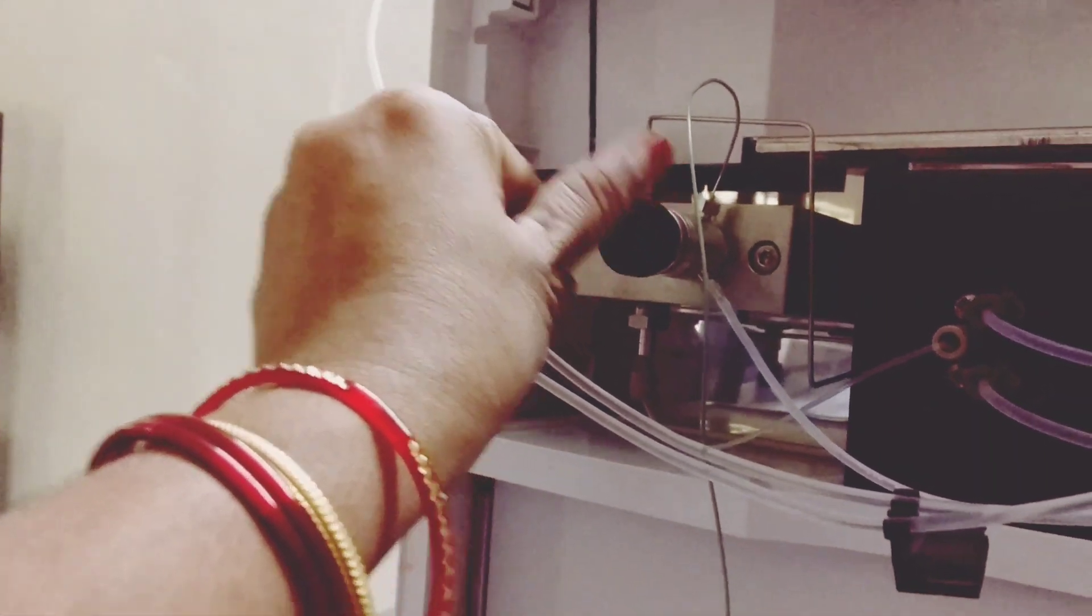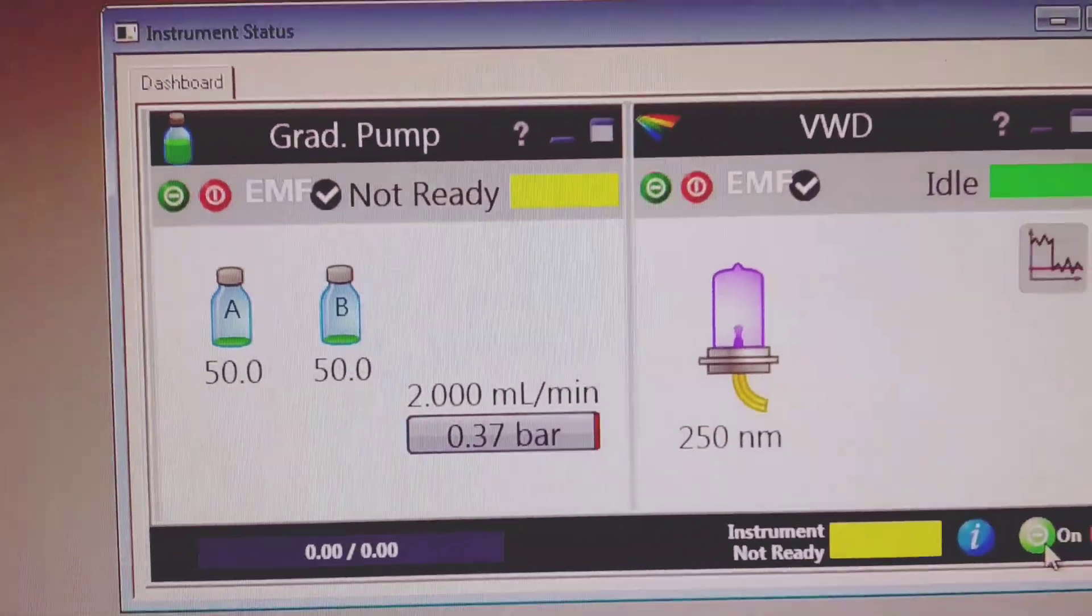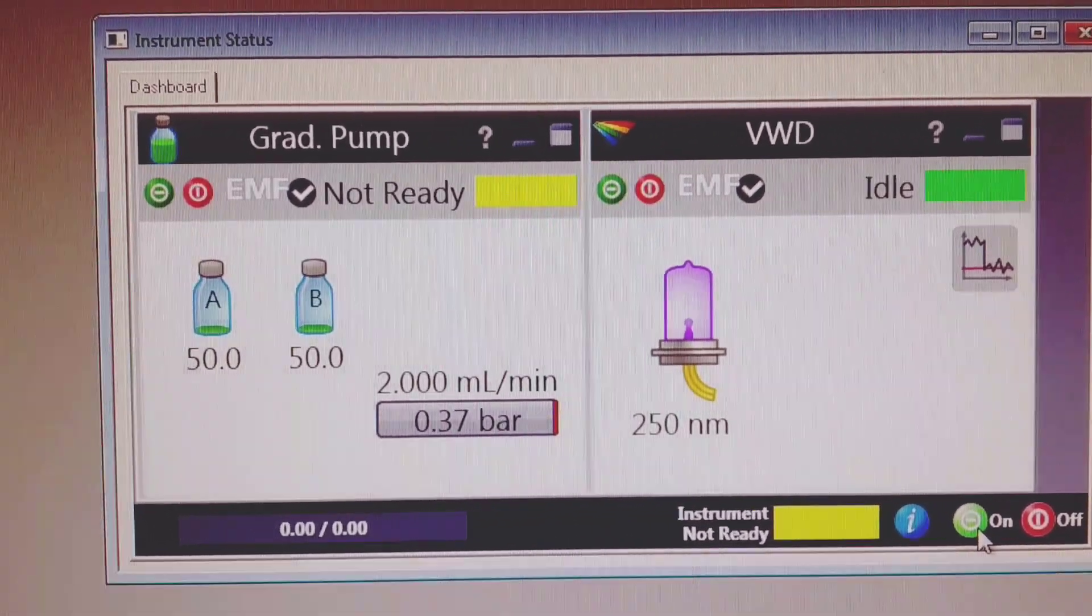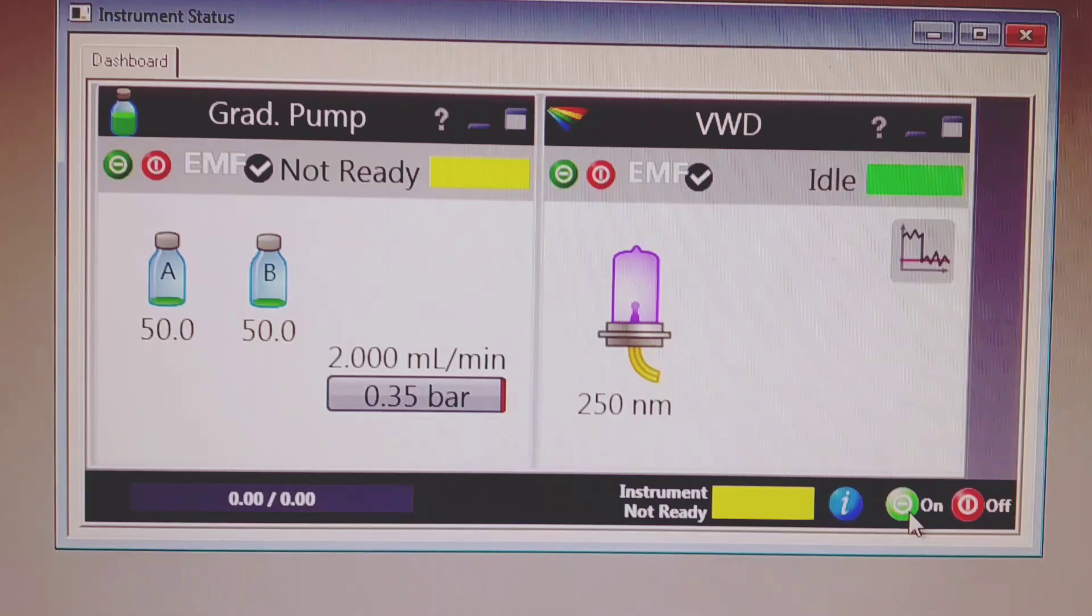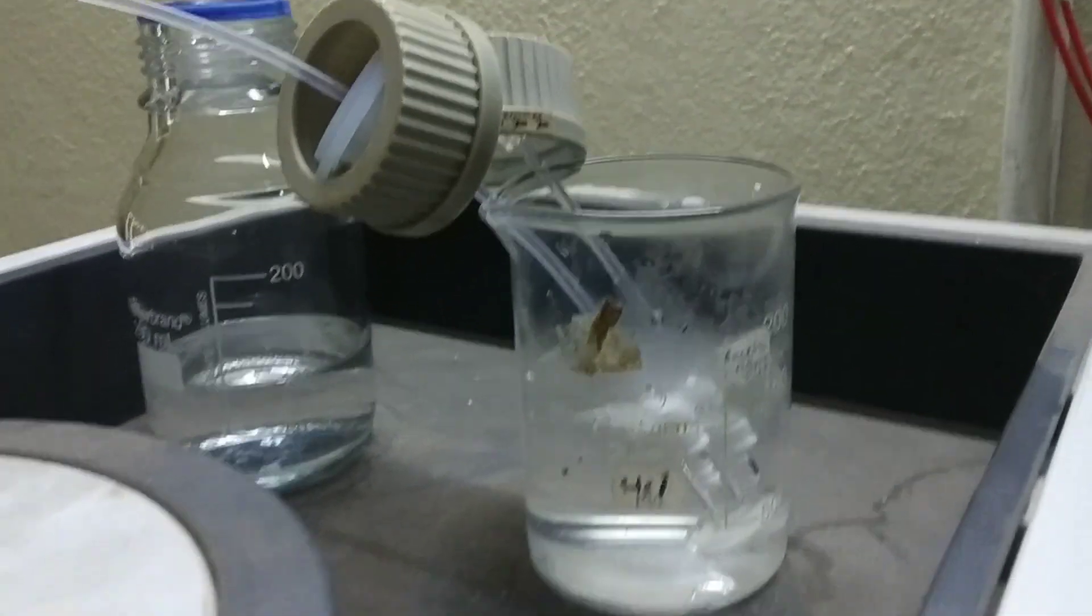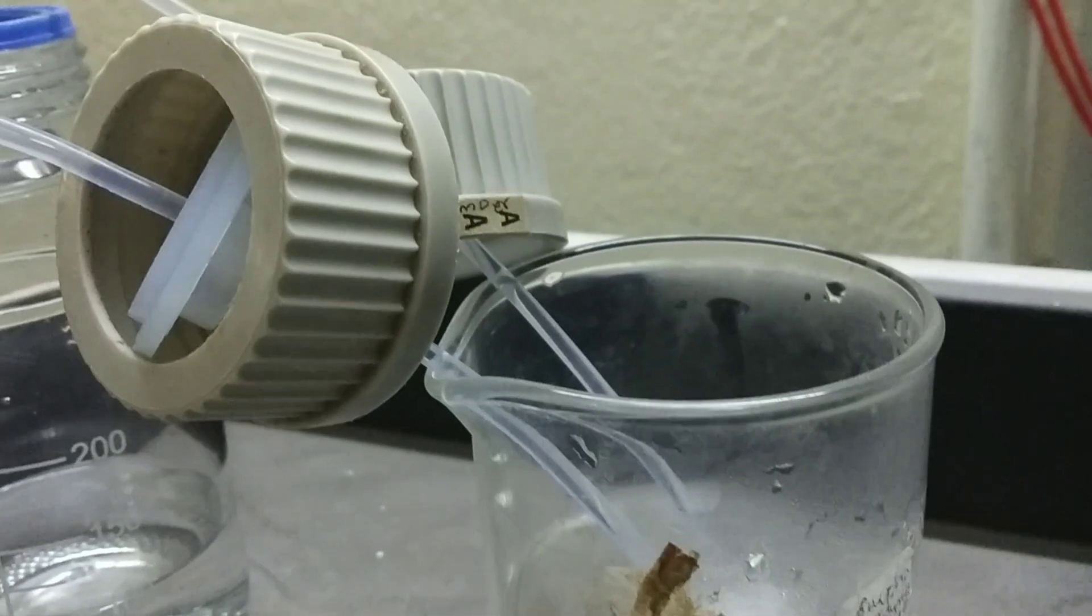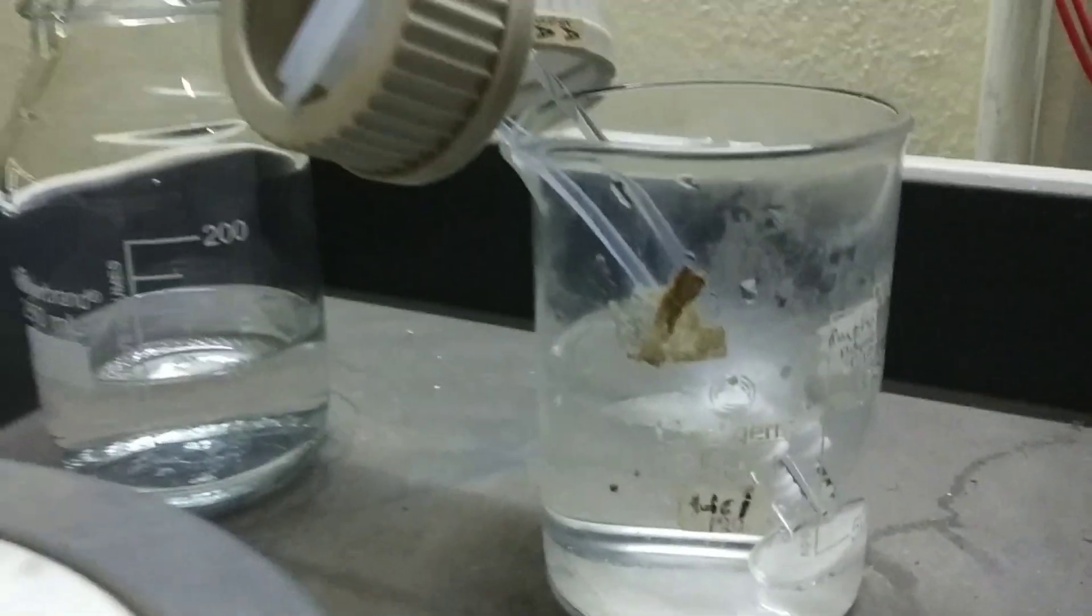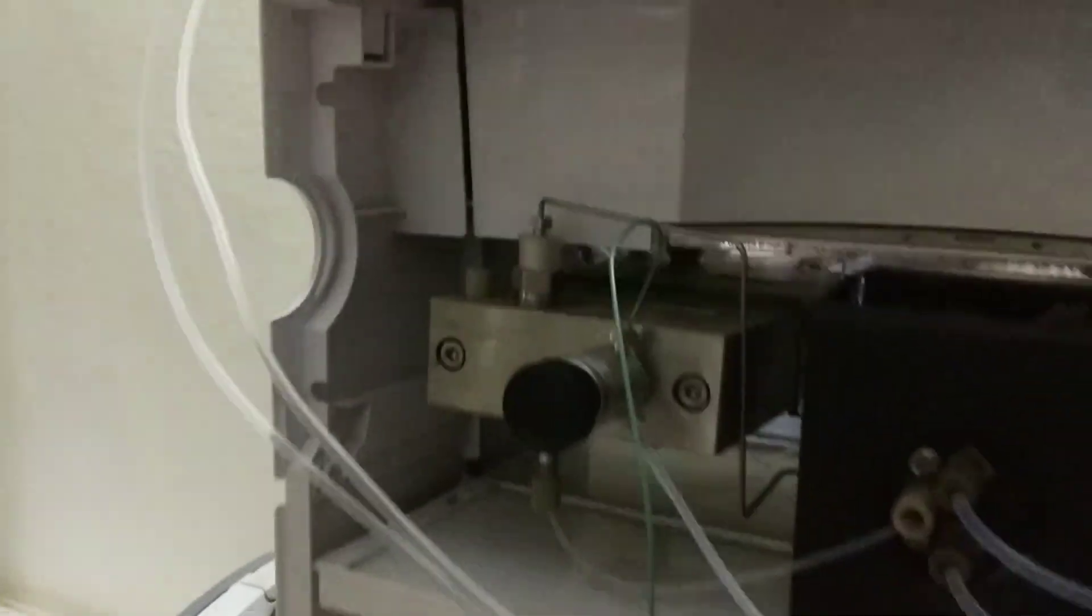As soon as I open the purge valve, you can see a decrease in the pressure—very less pressure you can observe here—and the flow rate is around 2 ml per minute. I have kept both the filters of the two reservoirs into a single beaker containing HPLC grade water. The objective of this purging is simply to flush through all the lines so that any remaining solvent from a previous analysis is replaced with new mobile phase.